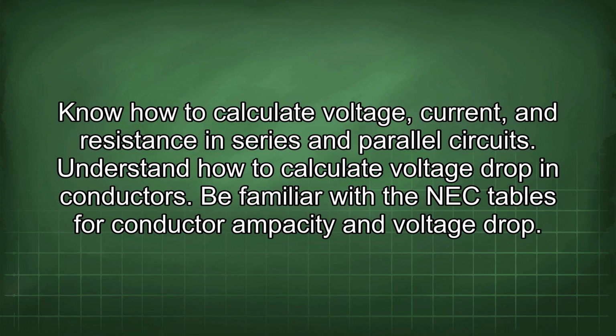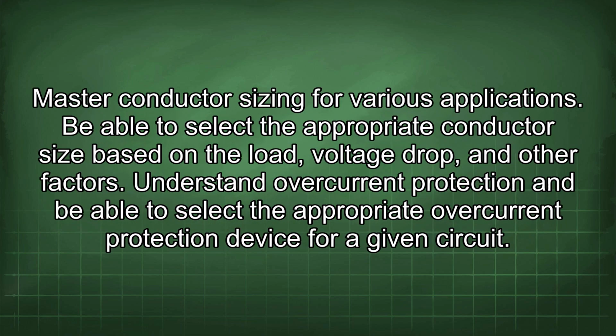Understand how to calculate voltage drop in conductors. Be familiar with the NEC tables for conductor ampacity and voltage drop. Master conductor sizing for various applications. Be able to select the appropriate conductor size based on the load, voltage drop, and other factors. Understand overcurrent protection and be able to select the appropriate overcurrent protection device for a given circuit.